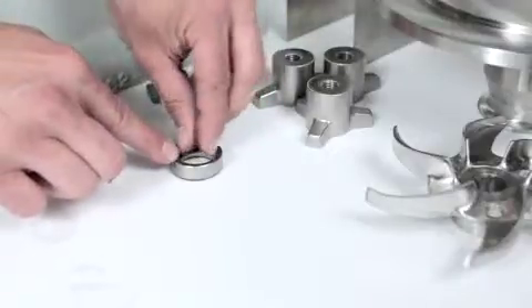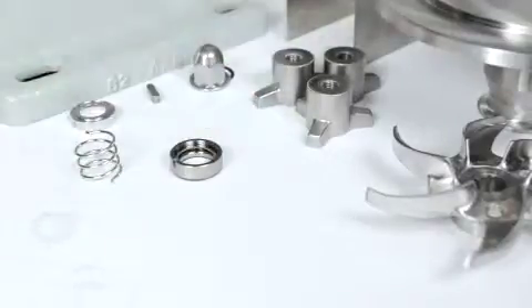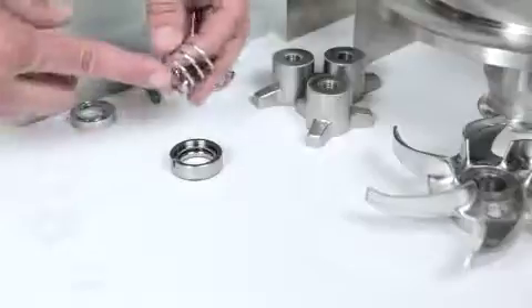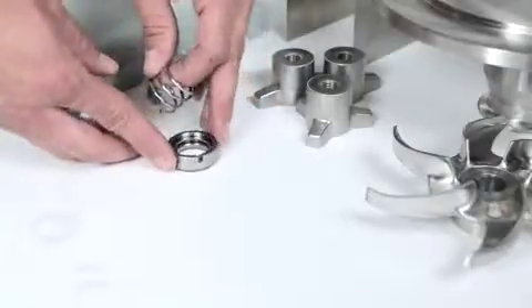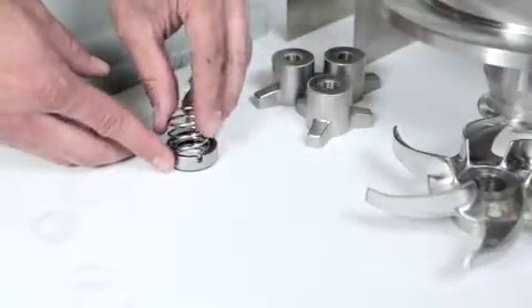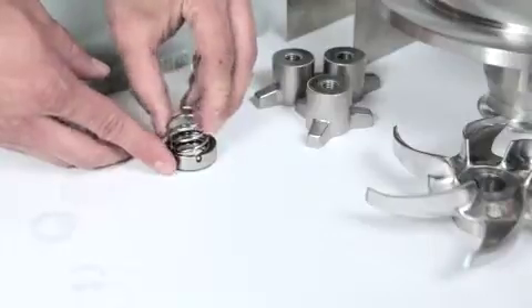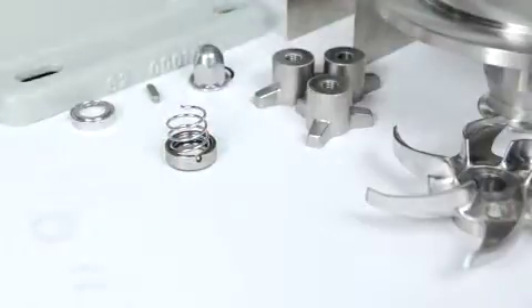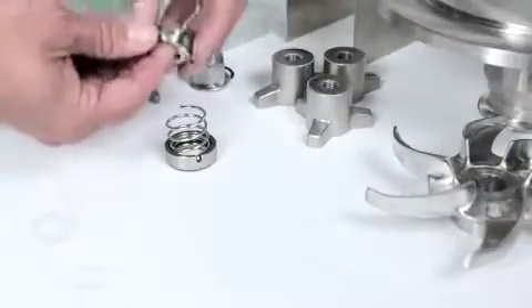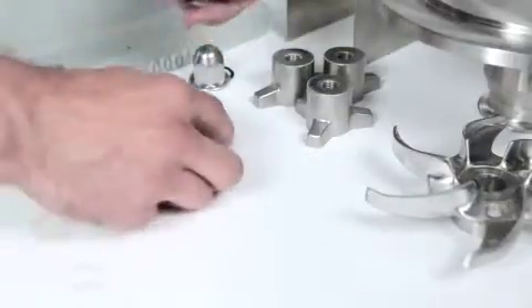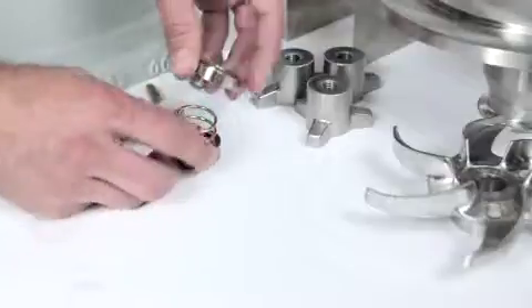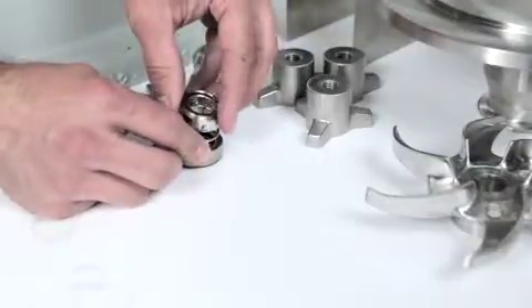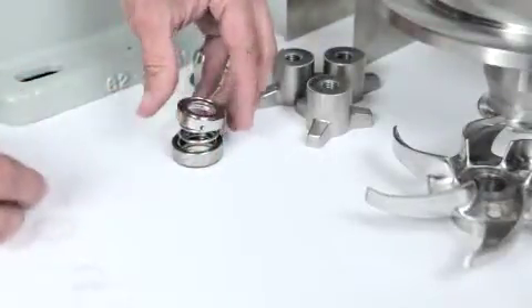Now, place the seal washer into the rotating seal. Next, install one end of the seal spring into the rotating seal, making sure that the tab of the spring is in the slot of the rotating seal. Finally, install the tab on the other end of the seal spring into the hole on the front seal driver. The rotating seal assembly is now ready to be installed onto the pump shaft.